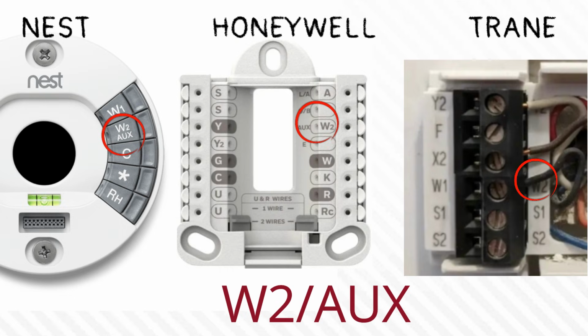W2 is typically used on two-stage heating systems. So if you have a gas or a propane furnace or electric heat strips, with two banks of heat strips, this second stage will kick in when the thermostat has not reached its heating set point for maybe 10 or 15 minutes. It will activate that second stage to generate more heat to get the temperature up faster. The auxiliary terminal can also start a gas or propane furnace or electric heat strips, but it only does this on heat pump systems when your heat pump is going into a defrost cycle and a secondary source of heat has to kick in during those times. So you're either dealing with a second stage of heat or a second source of heat.